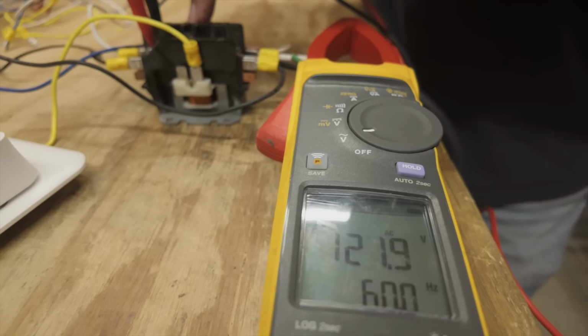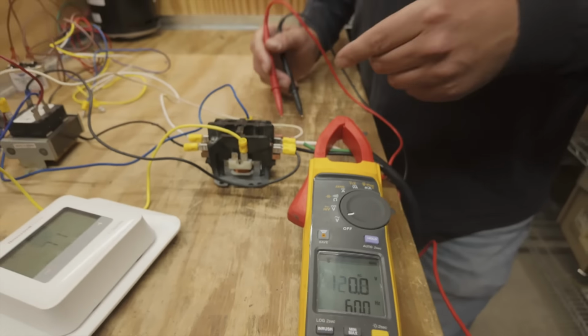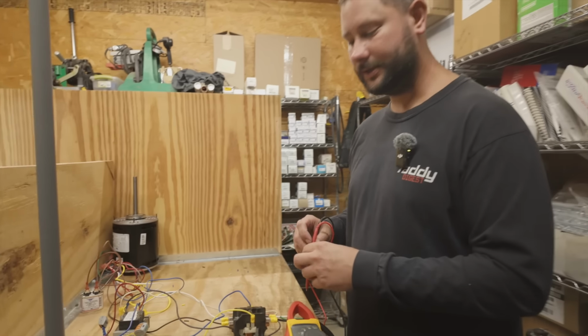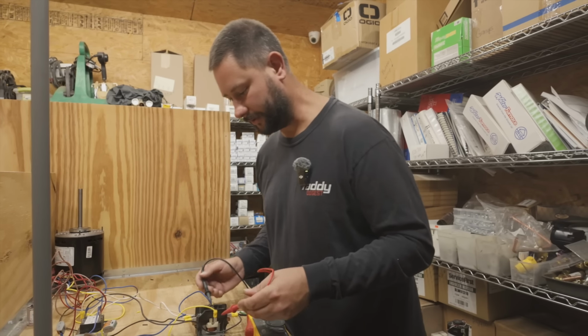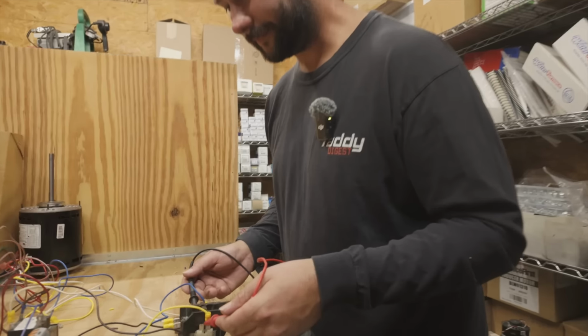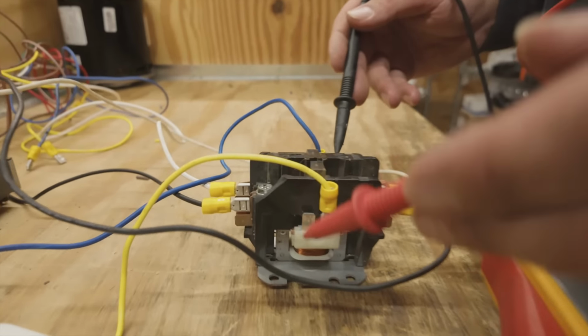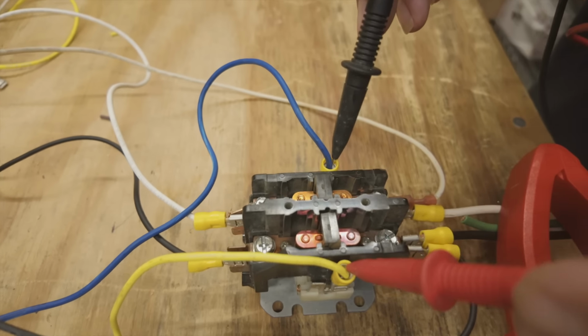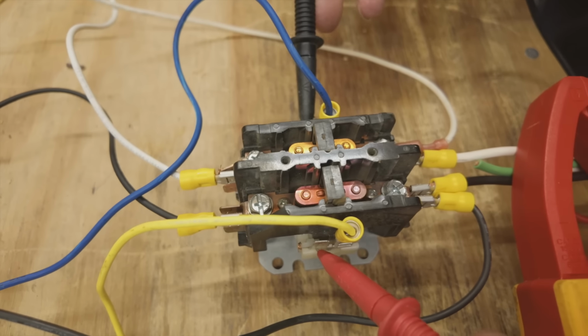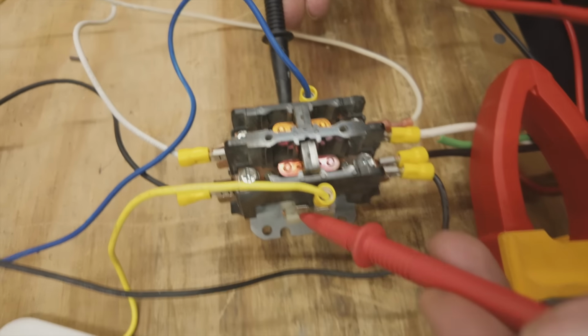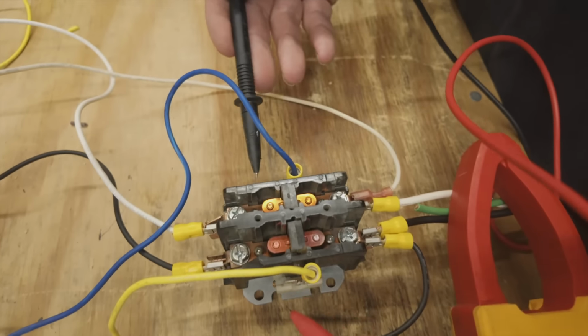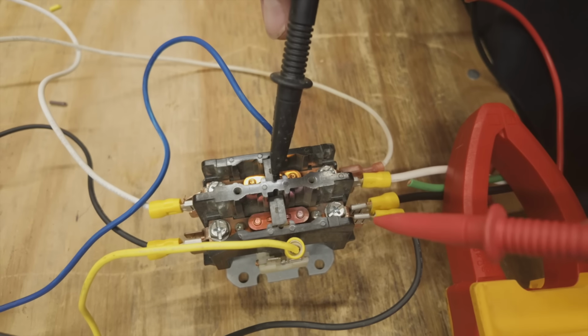There's 120, right? Now, what pulls this in is the coil getting voltage, and the coil is right here. See where the blue and the yellow wire are? Right here. If I check, the coil doesn't have voltage. See my meter? 0, okay? When this has voltage, this will pull in, and then we'll have 230 over here.